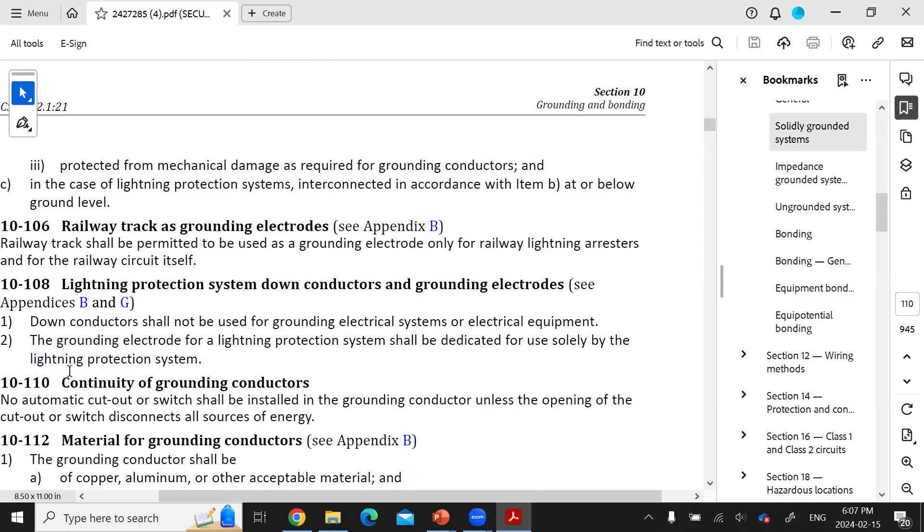The interconnection conductor between the two of them is to be protected from mechanical damage as well. So that means let's make sure that that is a buried conductor that's going to go from one electrode to the other electrode. Let's install it below grade for it to not be damaged.